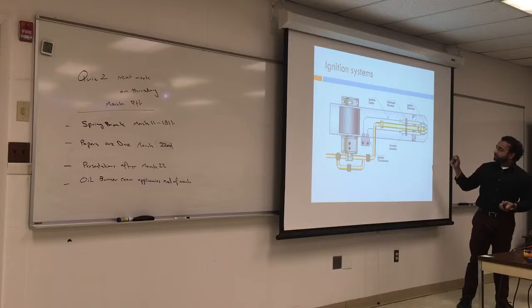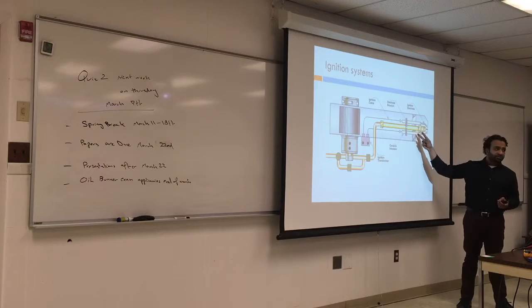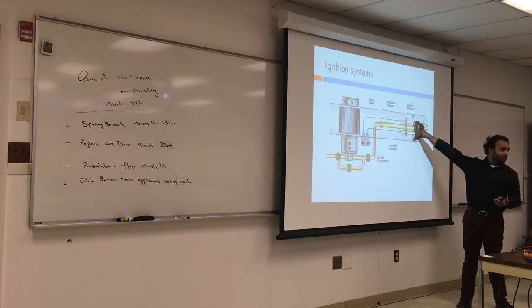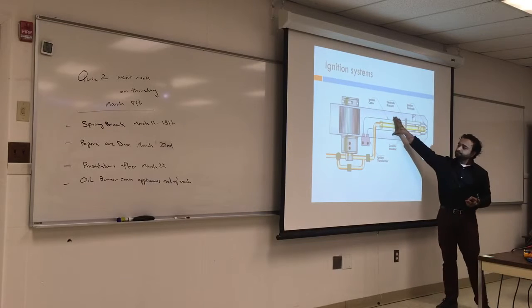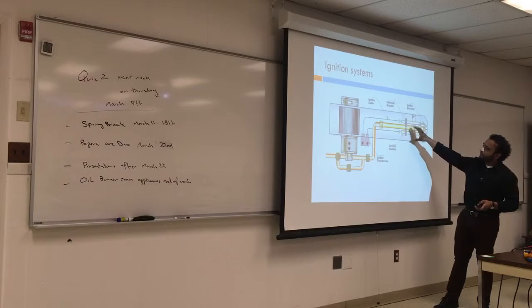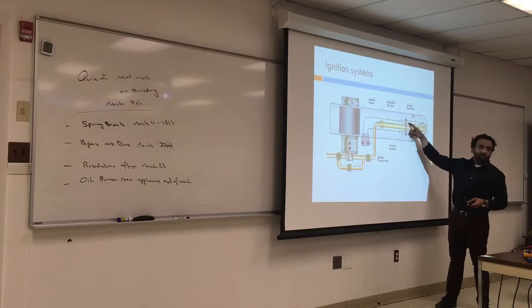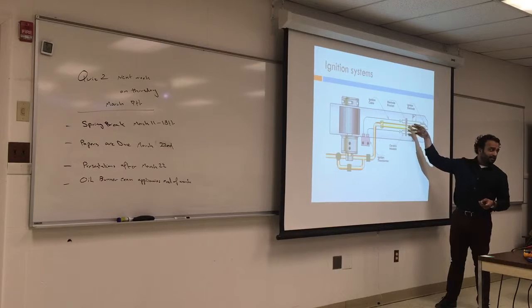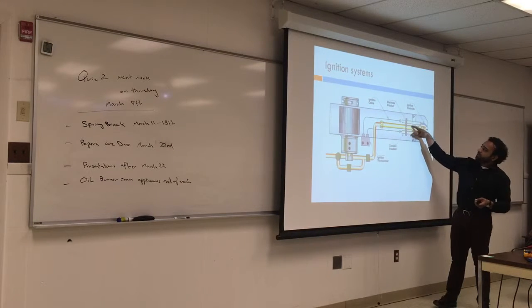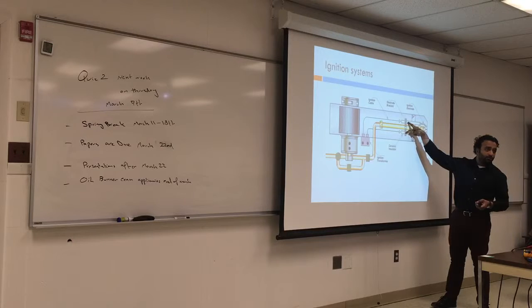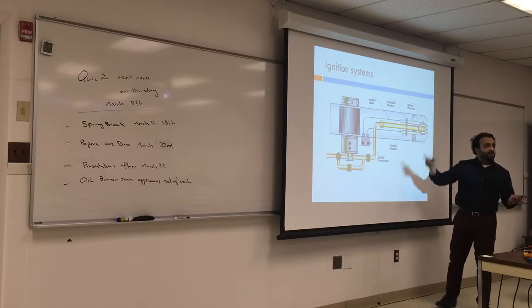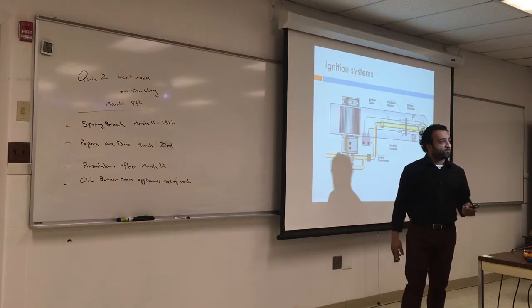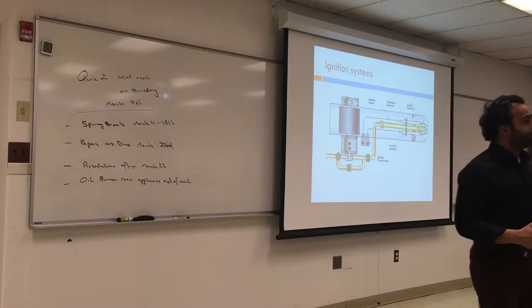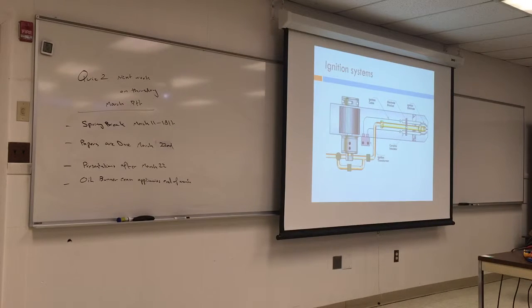Also, did you notice that the igniter has to sit snug inside the neck here, the extension, and it's really easy to remove? If they're wobbly, that's not a good thing. You want it to be steady. The ceramics could be broken or old or cracked. Sometimes you might have back flame, but it's not the right distance from the flame, so they get overheated, and by doing so, they will start to crack the ceramics.